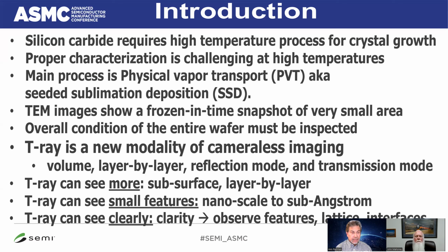So T-ray as an alternative not only can image the whole wafer, but also can see layer by layer across the depth without a destructive technique, without breaking it. No sample preparation is needed. So it can get the volume image, layer by layer, and imaging can be done both in reflection mode and transmission mode.